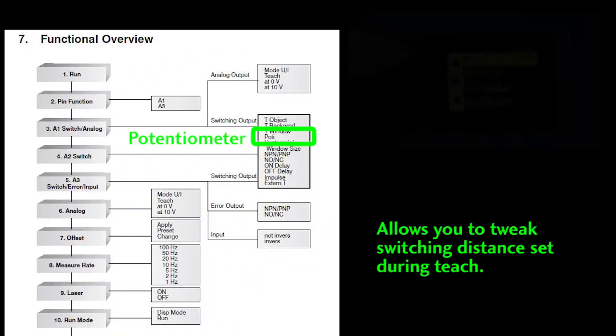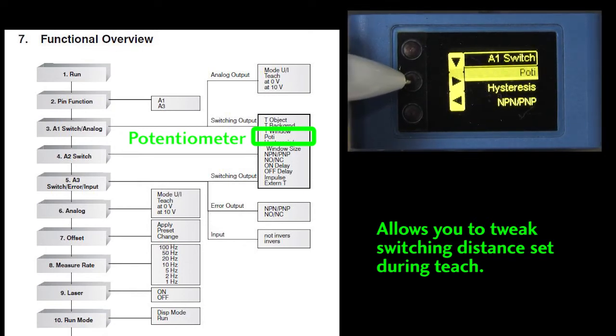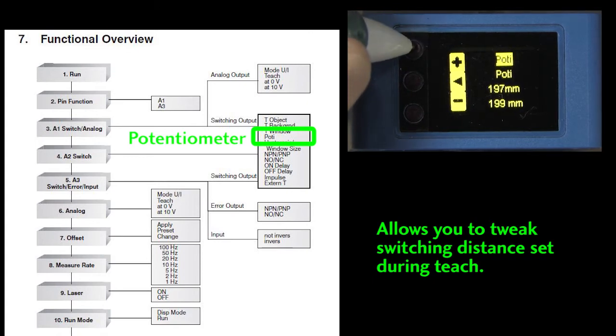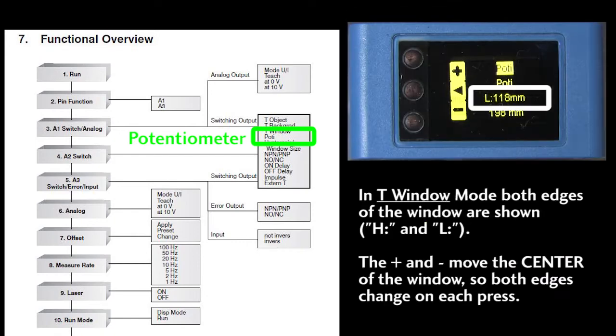This Poti command – I assume that stands for potentiometer – allows you to tweak the trigger point for all of these. For example, if your setup configured the sensor to trigger at 197mm and you need to bump that up a few millimeters, just drop into this menu and tweak it. If you have the sensor set to the teach window mode, you will see it toggle between the two window edges like this. The plus and minus signs tweak the center of the window so you will see both the high and the low change each time you press one.